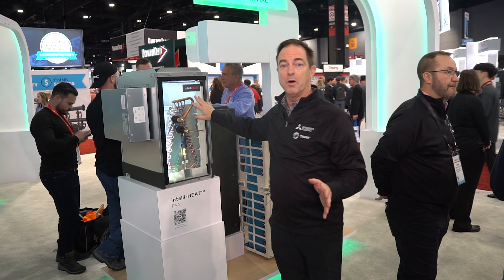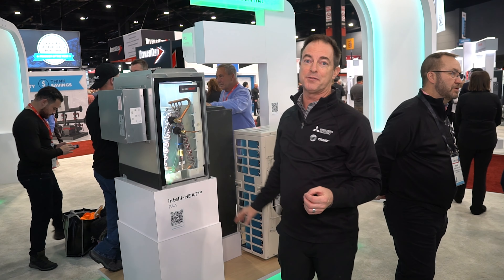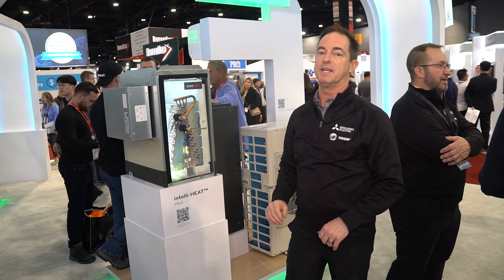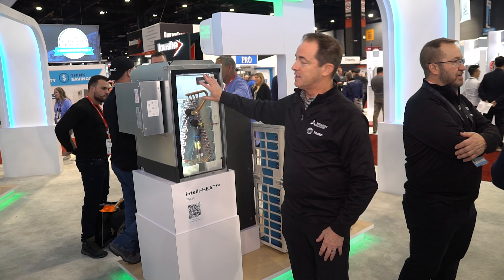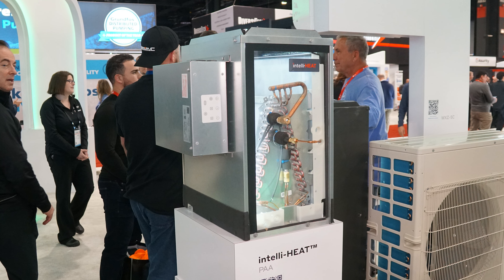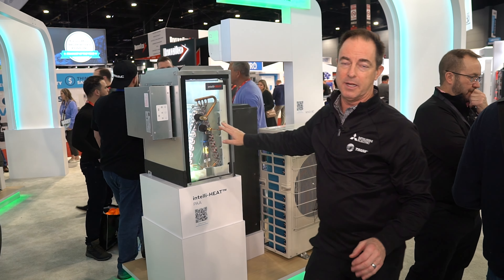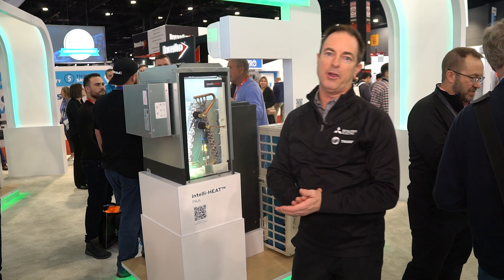I'm standing right next to our latest heat pump product. This is our Hyperheating SUMO product. The innovation here is that we're able to take this all-climate heat pump down to minus 22 degrees and provide a hundred percent of heating capacity at minus 10. As well as the heating performance, I also want to showcase the efficiency. The system is designed to be 35 SEER, so not only are you getting that heating performance in those low ambient conditions, you're also getting very efficient cooling performance.